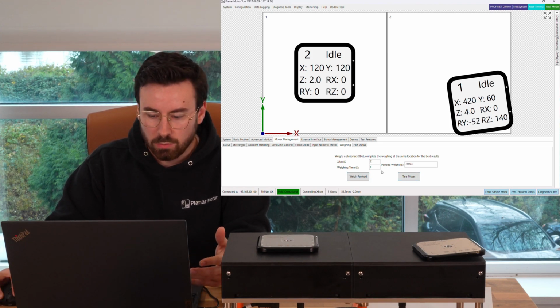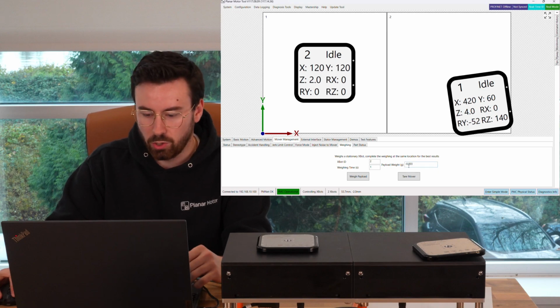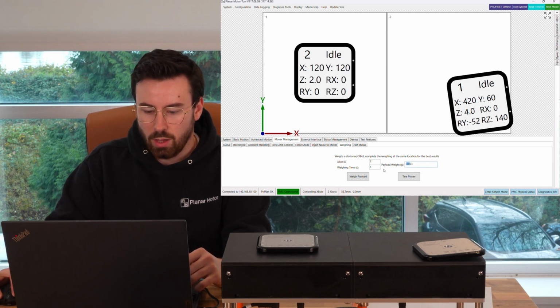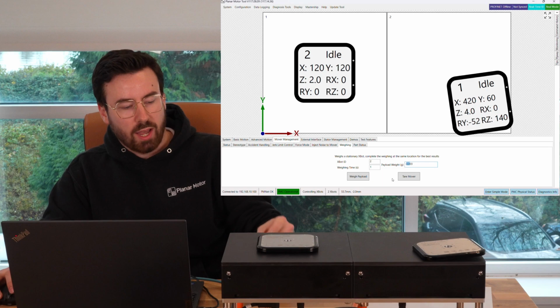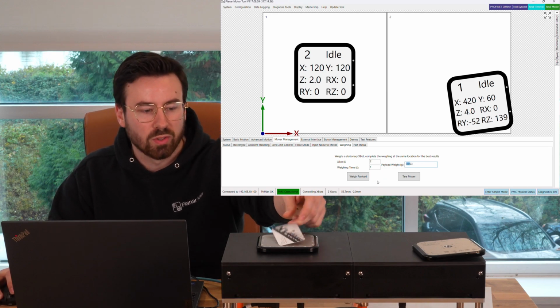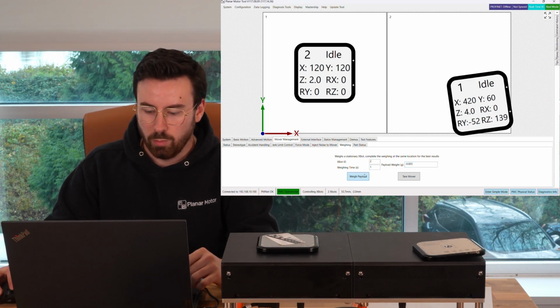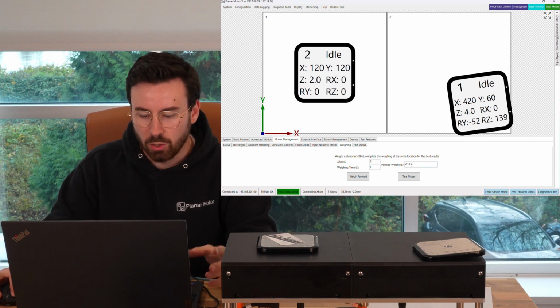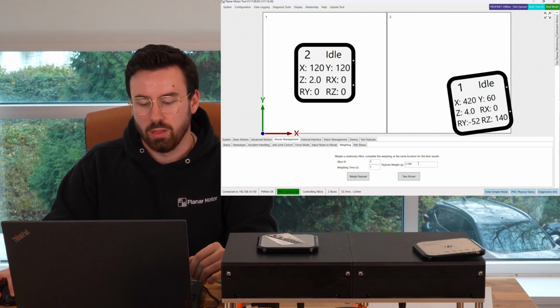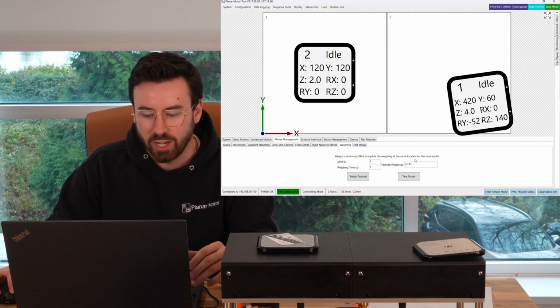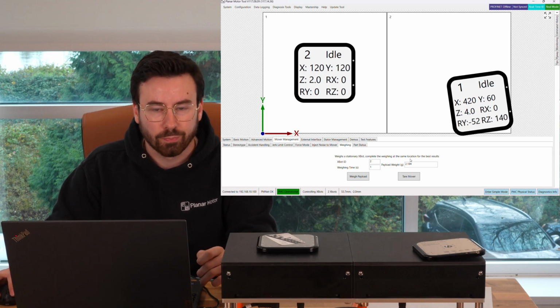Now if I'm weighing, we see roughly 0 grams with a little bit of noise. And so now once I add a little bit of weight in the form of this business card and weigh the payload again, we see, okay, roughly 2 grams. That makes sense. The card clearly was recognized by our system.